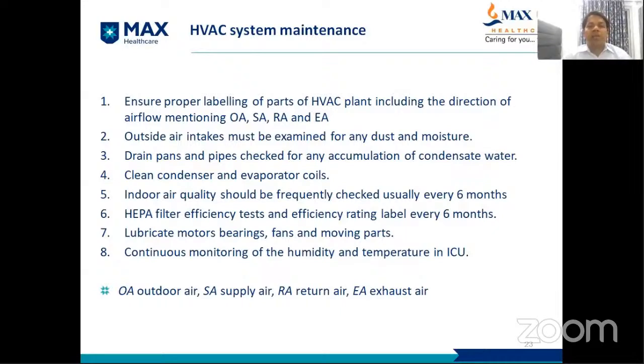Outside air intakes must be examined for any dust and moisture. Third, are the drain pans and pipes checked for any accumulation of condensate water? Fourth, clean condenser and evaporator coils. Fifth, indoor air quality should be checked frequently, usually every 6 months. HEPA filter efficiency tests should be checked every 6 months.